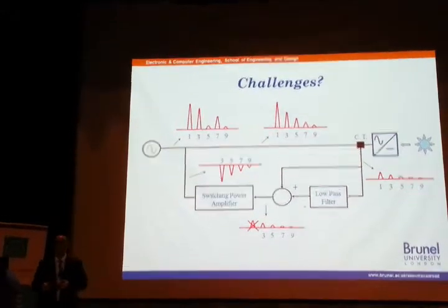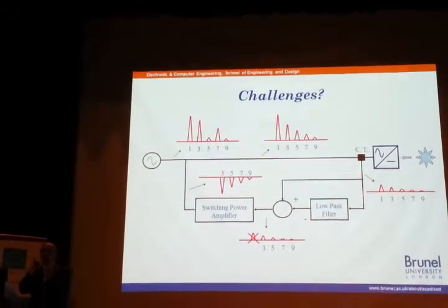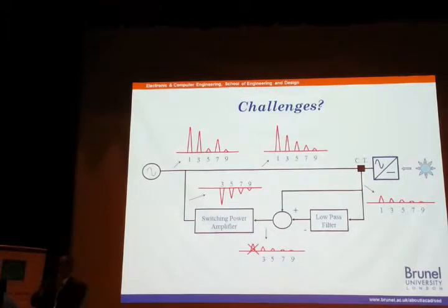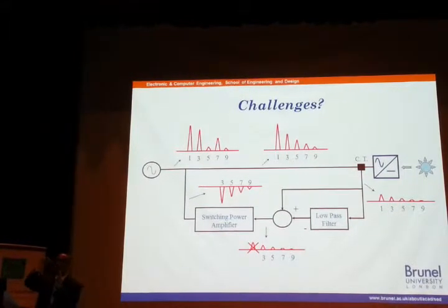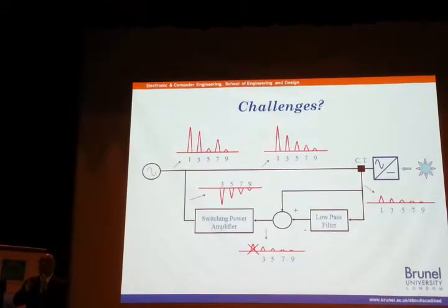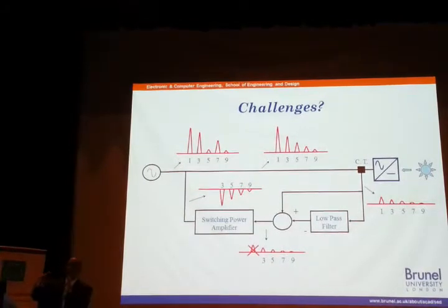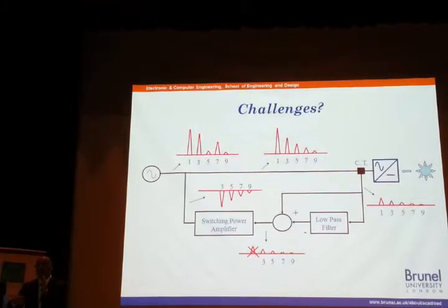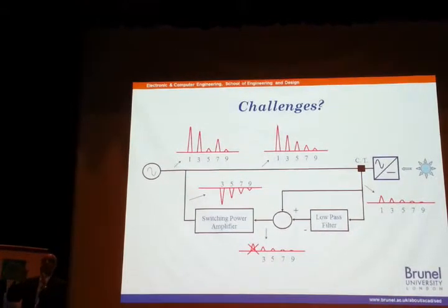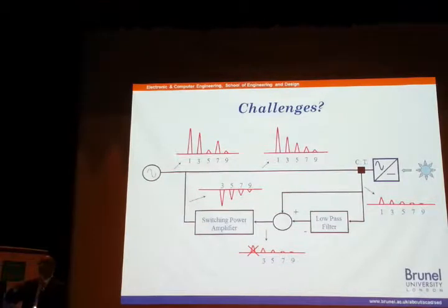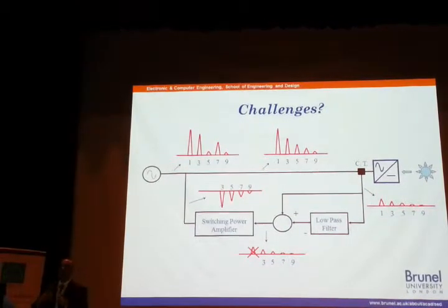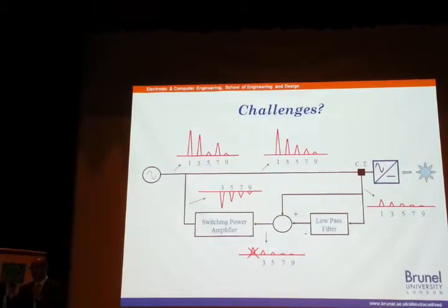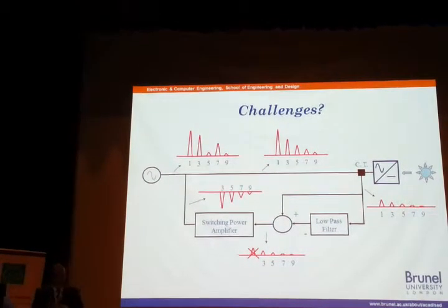Now, there is the wavelet transform, with which I can take a window. I don't have to wait for the complete cycle. I'll just sample it there and then try to predict by looking at the first, very, very small window. This waveform might contain such and such harmonics. Then I will send my control signal to the active filter saying that the waveform is likely to have that sort of harmonics, and then it will act accordingly, okay? If it is not, then it will adjust itself as we go all the way, okay?